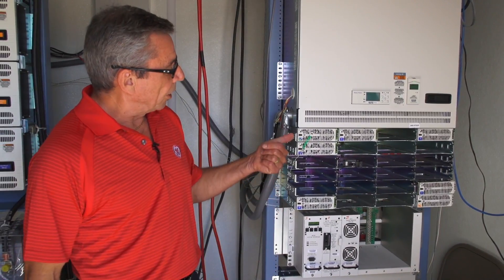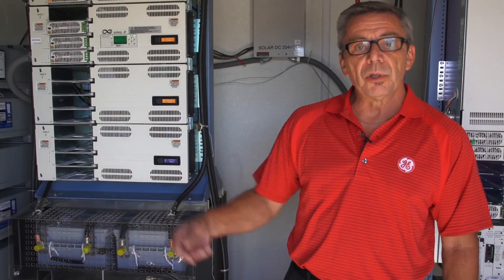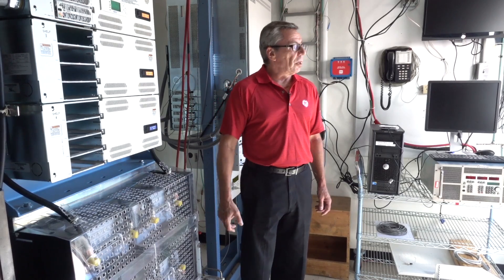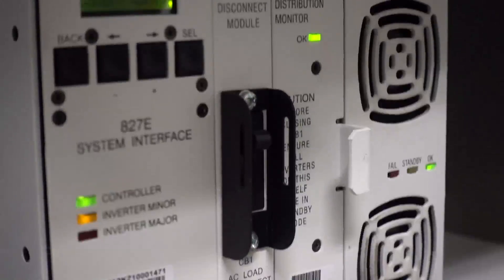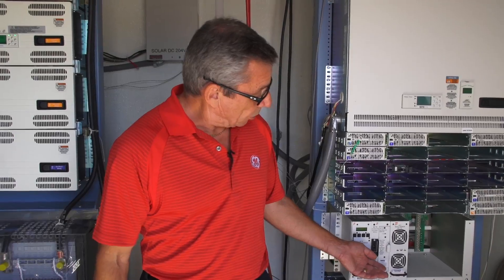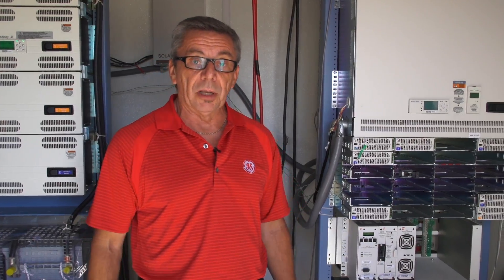The DC power system is converting energy from solar cells through these rectifiers to 48 volts DC, which is used in other systems, charging batteries, running loads, and operating other equipment here in this telecom wireless hut. We also have some AC loads, so we have inverters which allow us to power incidental AC loads as well as the primary DC loads.